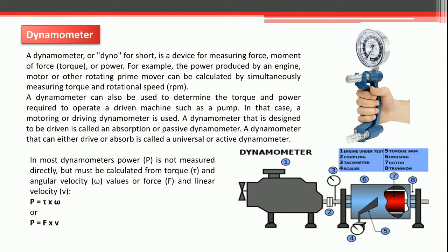If the dynamometer has a speed regulator, it also provides a variable amount of braking force that is necessary to cause the prime mover to operate at a desired test speed or RPM. Now power is calculated from the rotational speed times torque times a constant, with the constant varying depending on the output unit desired and the input unit being used.